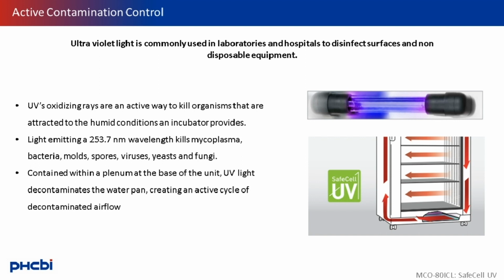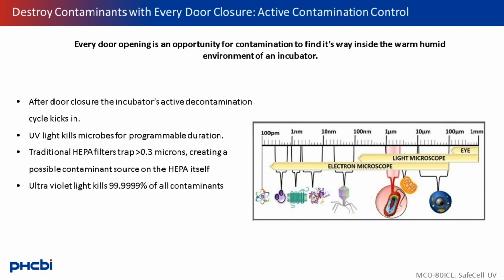Ultraviolet light has been commonly used in the lab to sterilize metallic surfaces and instruments that cannot be autoclaved. Light emitting 253.7 nanometers in wavelength destroys bacteria, molds, spores, viruses, yeasts, and fungi. Hidden behind a plenum wall, the UV penetrates the water and air that will flow through the internal chamber of the incubator. Again, opening the door allows contaminants attracted to the warm, humid environments to get into the incubator chamber. Once the incubator door is closed, the UV emits light that kills newly introduced contaminants from anywhere from 5 minutes to, depending on your user preference, a half hour.